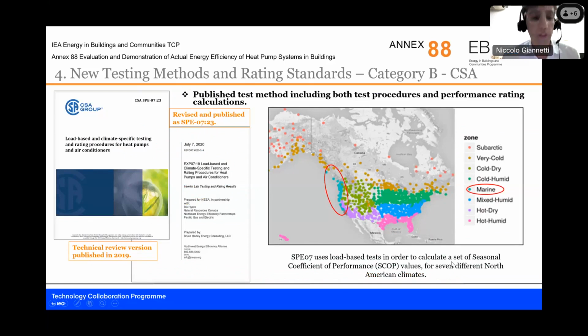So then very quickly on the other methods. So we have CSA's activity that also started around 2015 and focus on air-to-air unit tested with load-based test with a method that is used to calculate seasonal COP values for different climates, for example, those of North America. So their activity has been published 2 times. First technical review in 2019, already a draft of a rating standard procedure, and the most recent one, SPE 0723 in 2023. Sorry, this one.